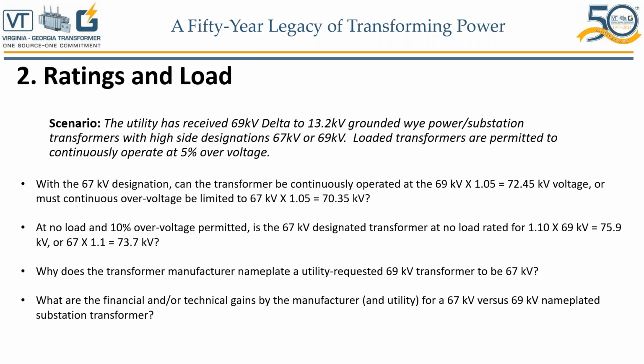It says, why does the transformer manufacturer nameplate utility request a 69 kV transformer to be 67 kV? It cannot be. If you wanted a 69 kV transformer, you should have gotten a 69 kV transformer, not a 67 kV transformer. So, because it's an open question here, I try to explain what I think I need to answer the question. I'm going to continue to the next slide, but once again, if the submitter of this question is online, please email me so we can get on a quick call and then answer more.